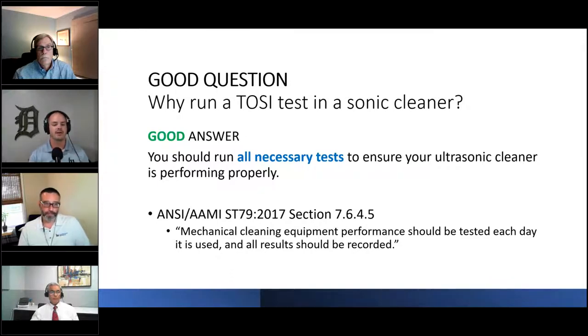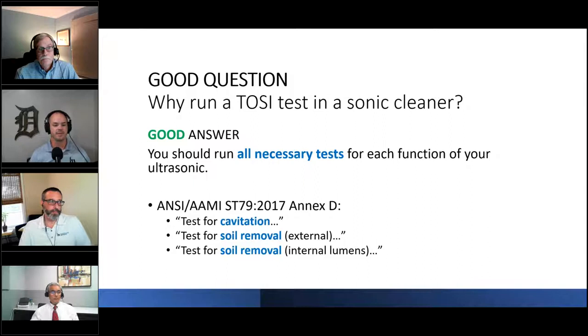But let's talk about more support for running these performance tests when we look at the next slide here. If you're familiar with Annex D of ST79, it gets a lot more specific about what tests to run in our ultrasonics. It states to test for cavitation, like we mentioned. It states to test for soil removal from external surfaces, and it also says to test for soil removal of internal surfaces like lumens or cannulated items, things like that.